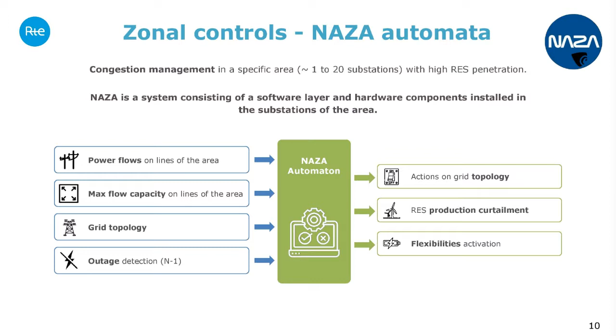For example, on max flow capacity, we deploy dynamic analytic devices. These devices can take into account the temperature, the wind, and the impact of wind on the temperature of the cables. If you have strong wind, you can have a lower temperature in the cables, and so more megawatts going through them.